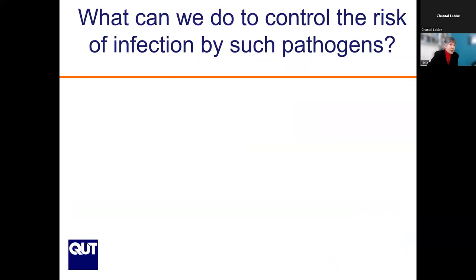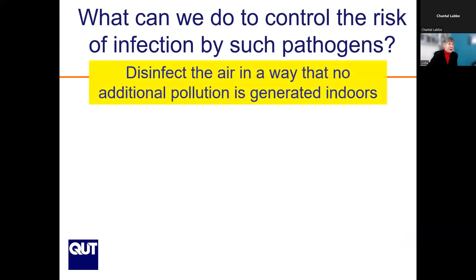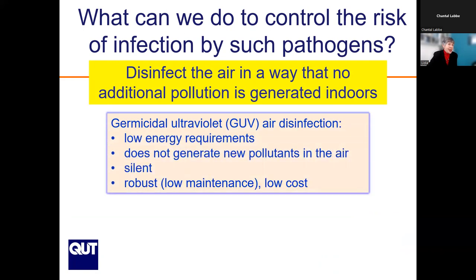WHO currently recommends 10 liters per second per person in shared spaces. The theoretical limit of what ventilation can do was presented as far back as 1991 by Ed Nardell — so this is not unexpected or new. We knew that with some very infectious diseases there would be a problem. Can we control the risk? We can. The solution is disinfecting the air in a way that generates no additional indoor pollution, using germicidal UV air disinfection, which requires low energy, does not generate new pollutants, is silent, robust, low maintenance, and low cost.